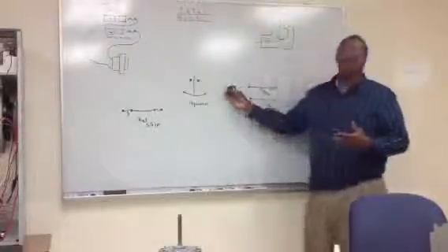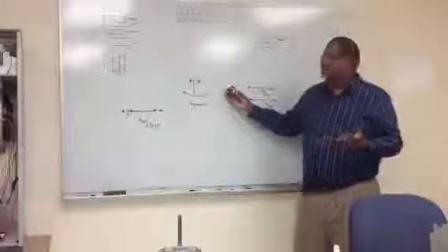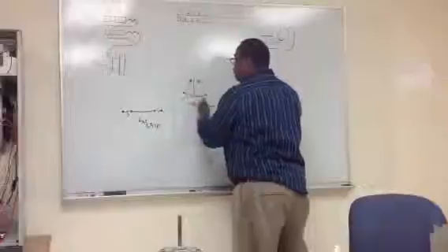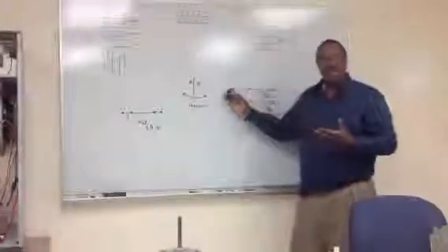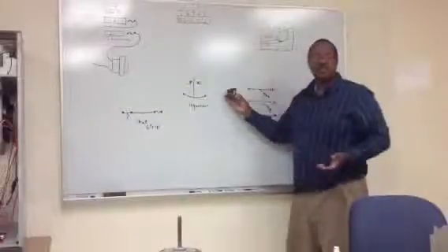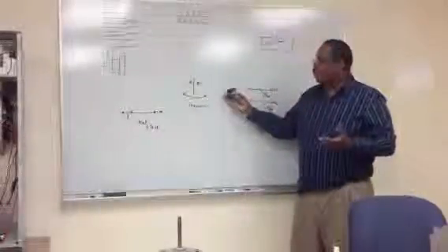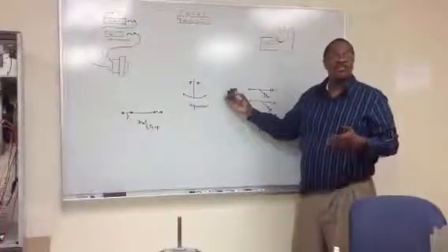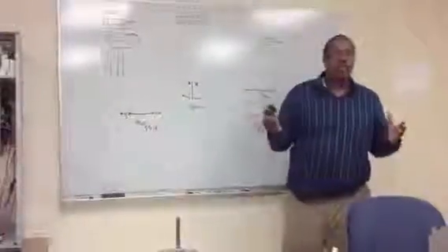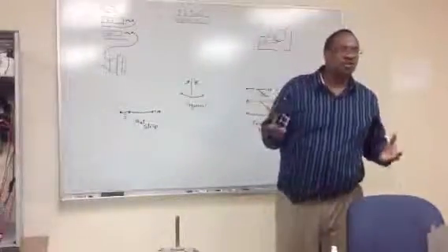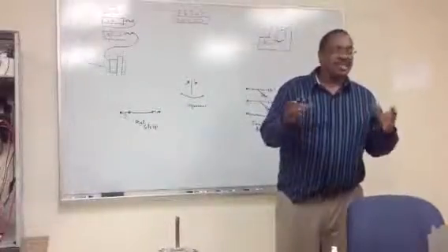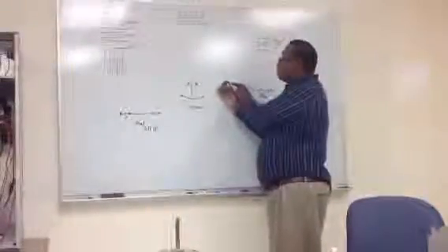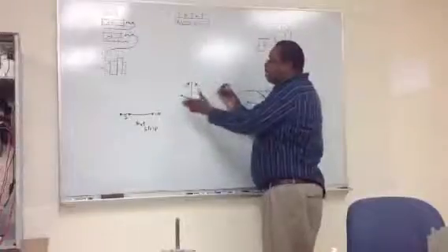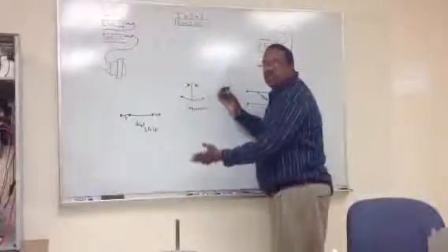Now, one thing about the sequencer, it is a time delay device. It consumes 24 volts at the bottom, and as it generates heat, it slowly moves and closes the contacts in the sequencer. The purpose of having a sequencer, a time delay device, to control the heat strips is this: have you ever gone inside a home and when the unit starts up, the lights in the house dim? Well, it's drawing too much current. All the heat strips are coming on at the same time. So the purpose of the sequencer is that each one of these circuits closes at a different point in time, allowing a different heat strip to come on at a different time.